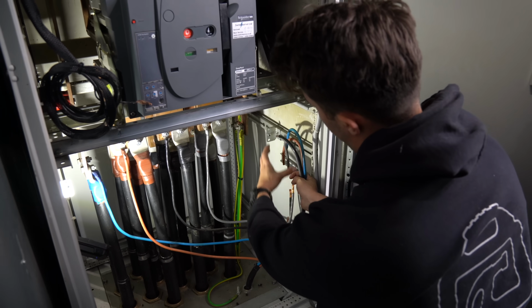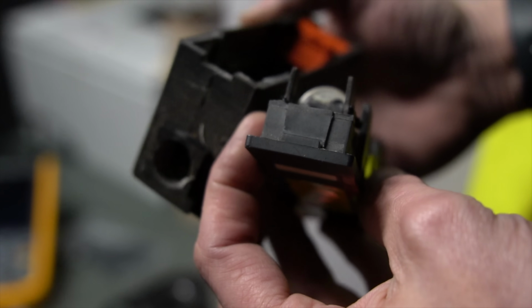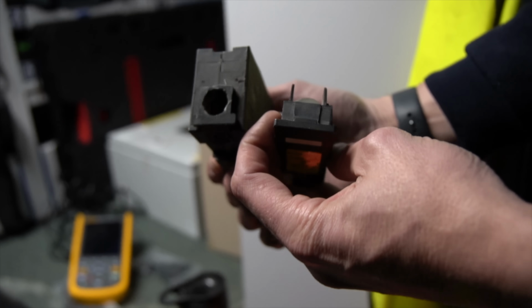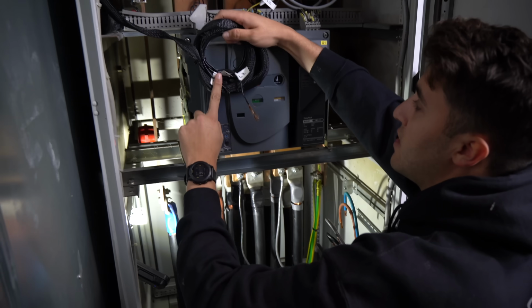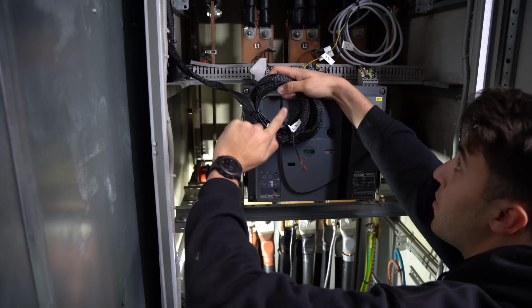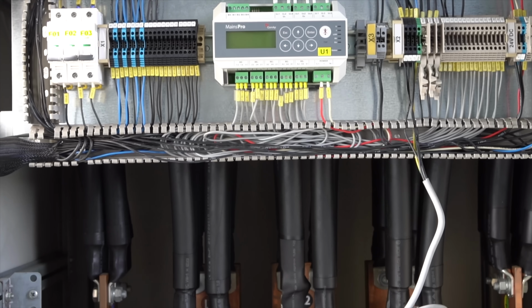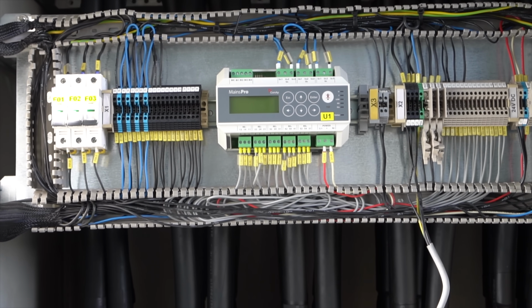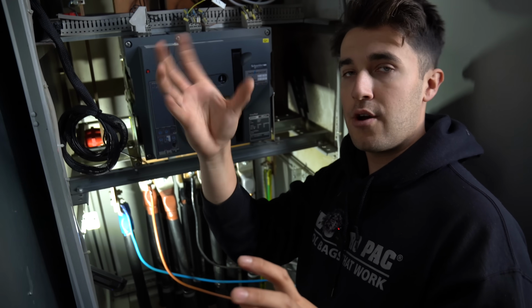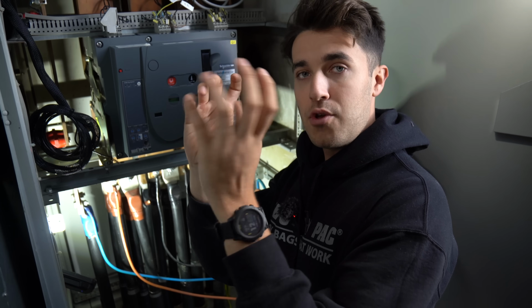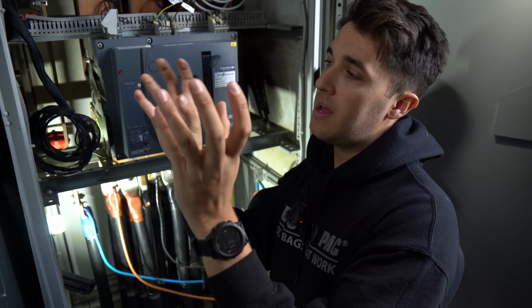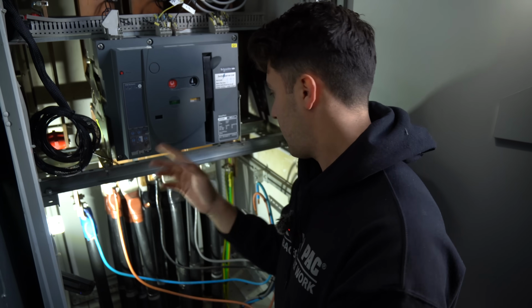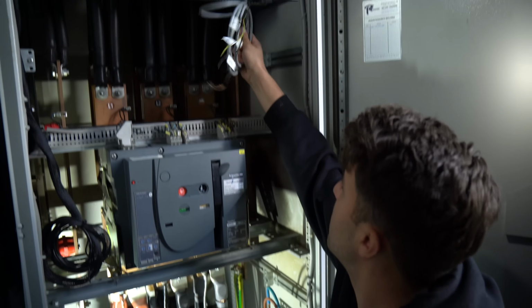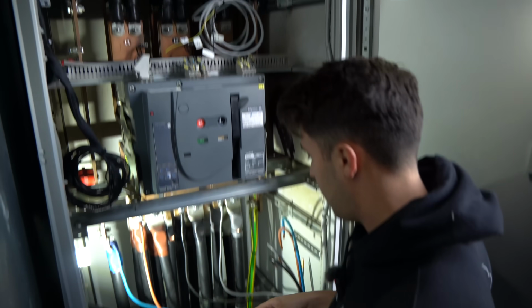There was a fuse carrier that sat there, but it wasn't just the feed in and feed out in there. You also had these cables here. This one goes over to a scope over there, which I'll show you later. And this one does a G99 device. So if you imagine the grid already has a generator somewhere ticking over, and you've got this one that's out, you can't then introduce that onto the grid. You have to wait until they're synchronized and then it will click and connect. That's what this cable was doing here.